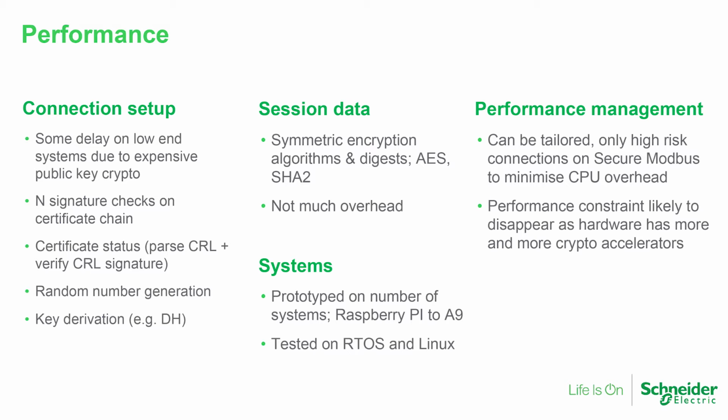But the good news is that for the actual session data, these are symmetric algorithms, and there's not a huge amount of data which needs to be exchanged. So during the actual session data, the exchange of Secure Modbus compared to Modbus, there will be a marginal performance cost. And in addition to this, we have ways to manage this performance question in that we don't have to migrate every data flow from Modbus to Secure Modbus. We can choose the high-risk data flows and migrate only those.